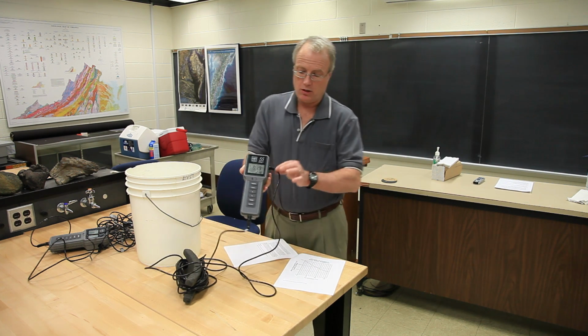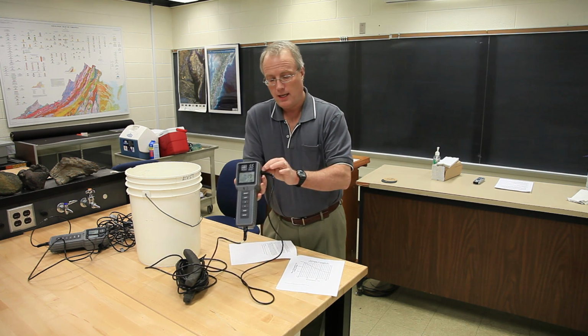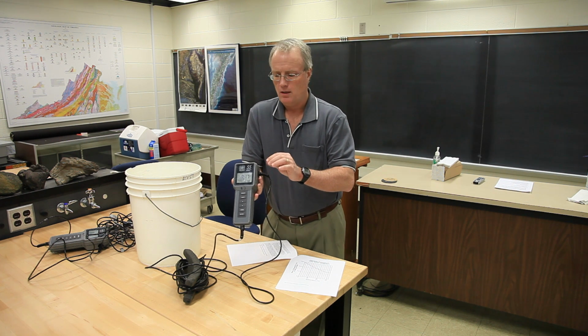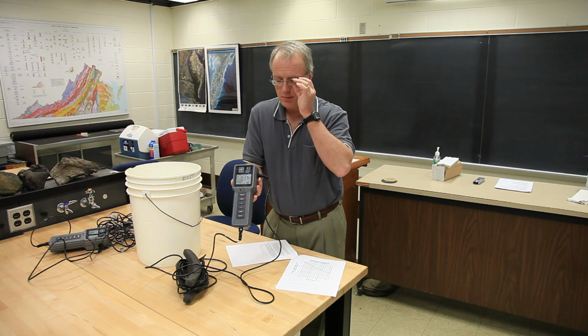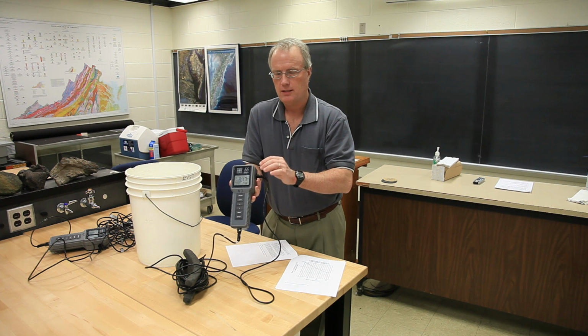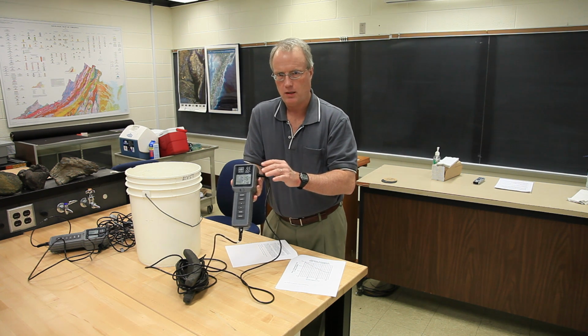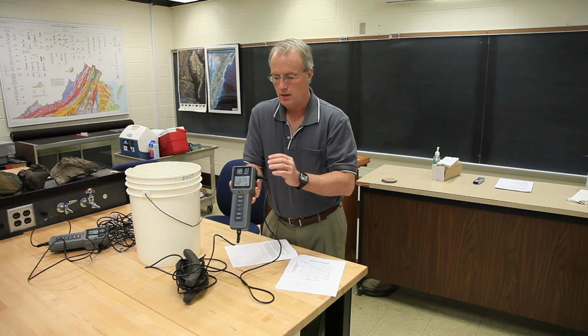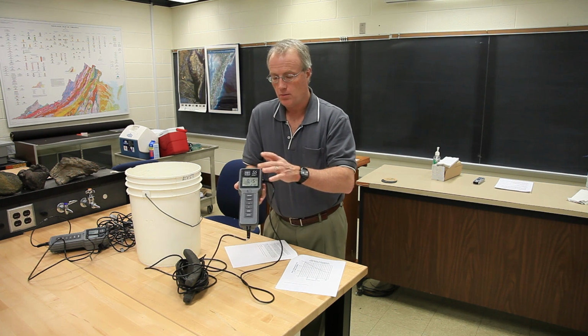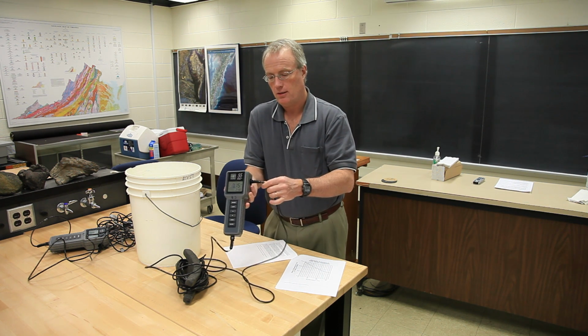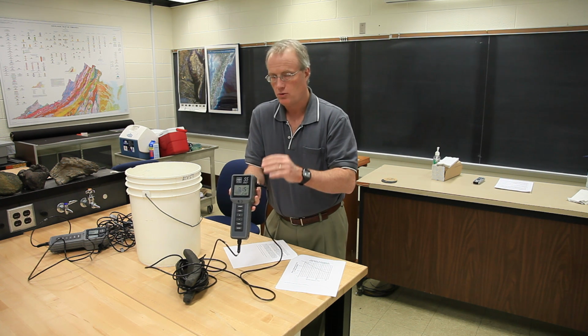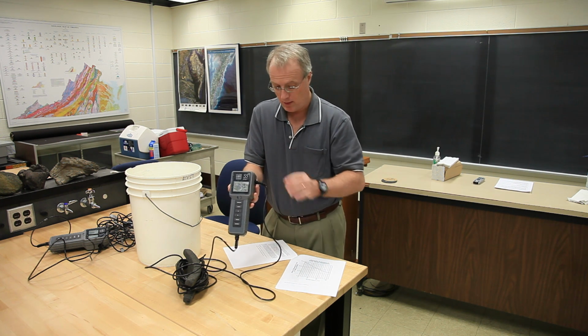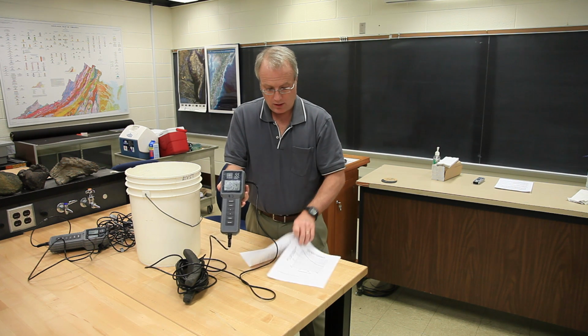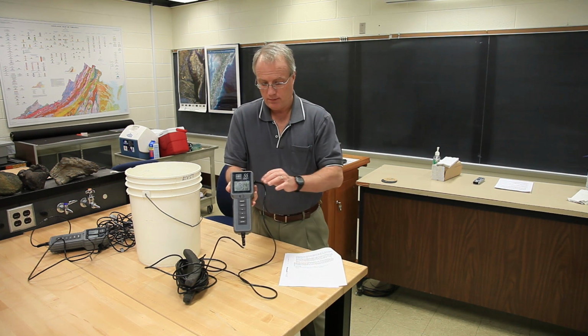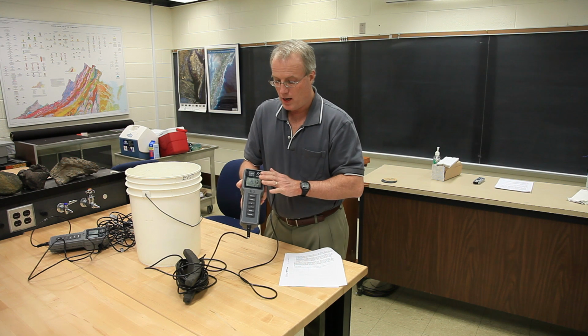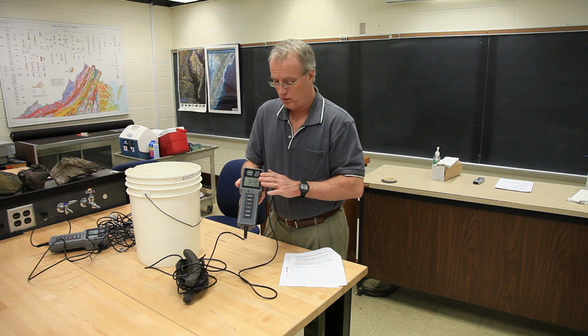All of the calibration occurs with the probe in the calibration chamber. This calibration chamber has to be wet. There's a sponge inside, and it needs to be fully saturated, not dripping, but fully saturated, to run the calibration. So the meter's been on for 15 minutes, and this probe has been in the saturated calibration chamber for those 15 minutes. You then simply follow the instructions for calibration, and when you get to the end, you now know that this meter is giving accurate readings.